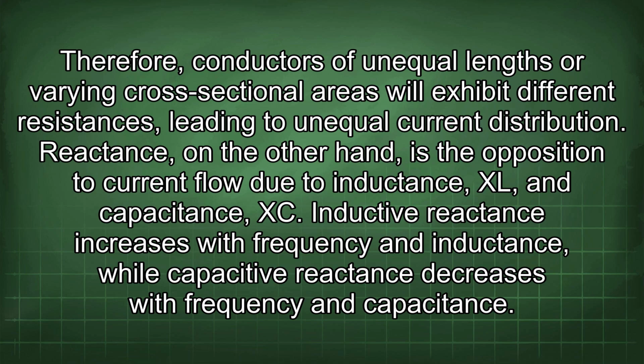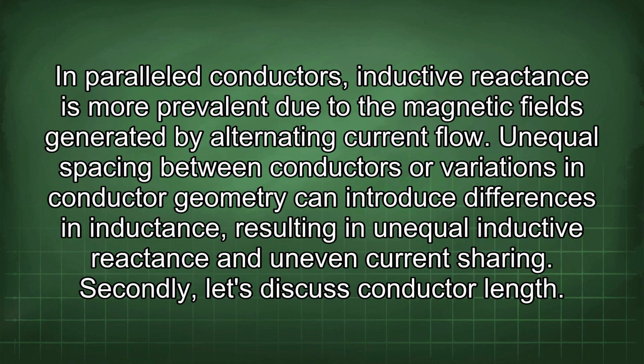Reactance, on the other hand, is the opposition to current flow due to inductance XL and capacitance XC. Inductive reactance increases with frequency and inductance, while capacitive reactance decreases with frequency and capacitance. In parallel conductors, inductive reactance is more prevalent due to the magnetic fields generated by alternating current flow. Unequal spacing between conductors or variations in conductor geometry can introduce differences in inductance, resulting in unequal inductive reactance and uneven current sharing. Secondly, let's discuss conductor length.